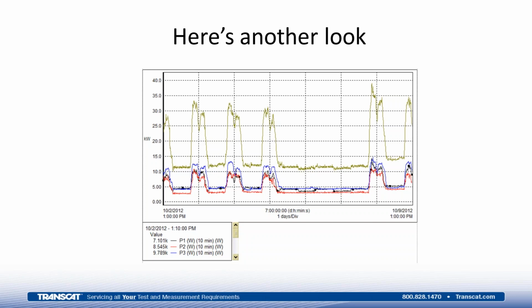Okay, what is meant by true RMS? I described that a little bit in the presentation, but just to go back over it again, when the utility generates a voltage, they generate a very, very pure sine wave. That sine wave is then delivered to your loads, and our loads are the cause of distortion. As the load draws from the source, it can distort the incoming source because of its loading of the transformer coming in. If we distort the waveform, the measurement of its energy has to be done with a much higher sampling. We have to be able to measure the distortion and take that into calculation when we're calculating energy.